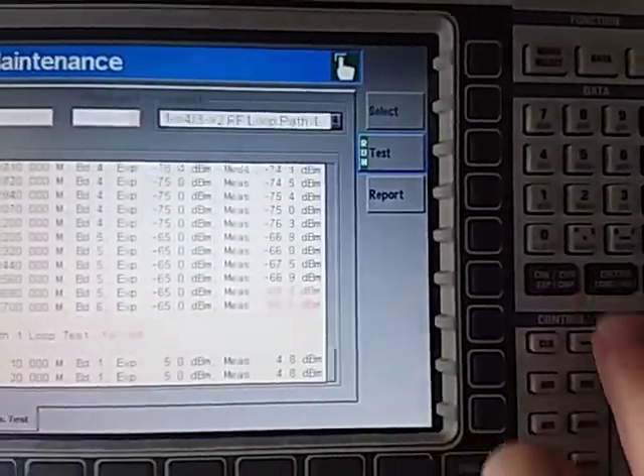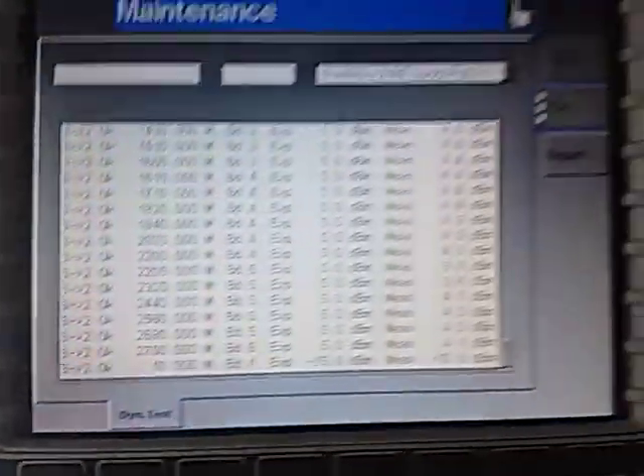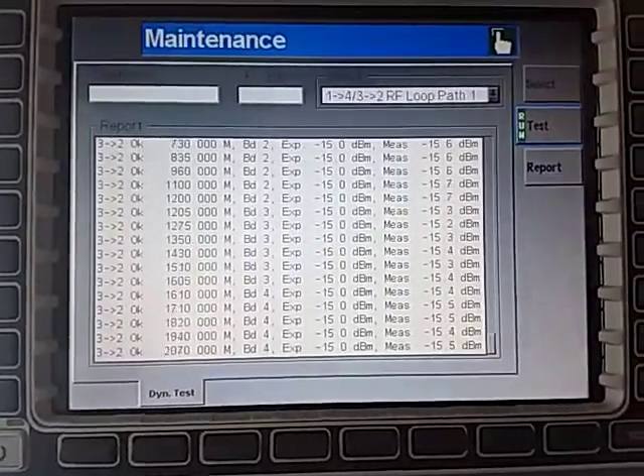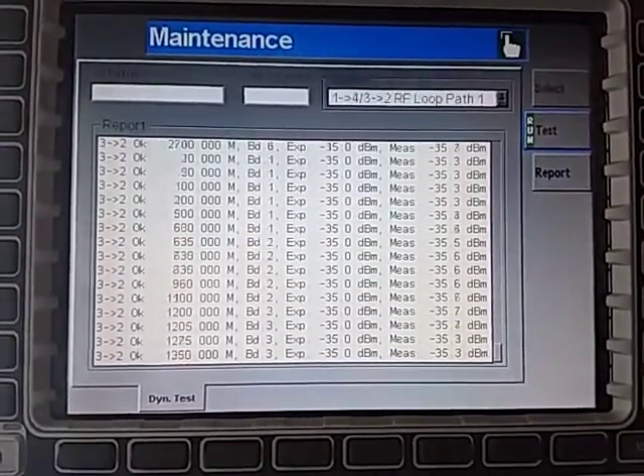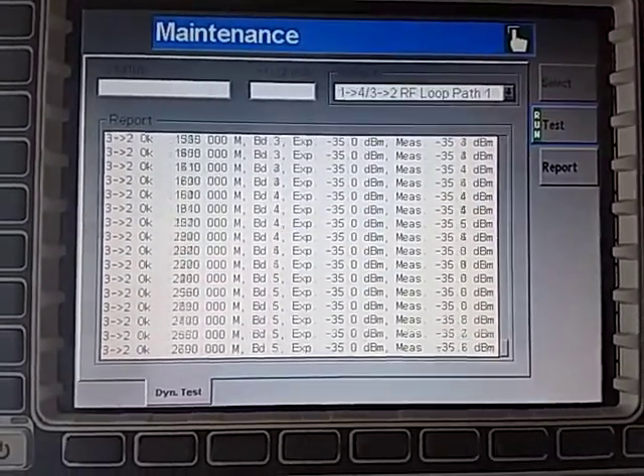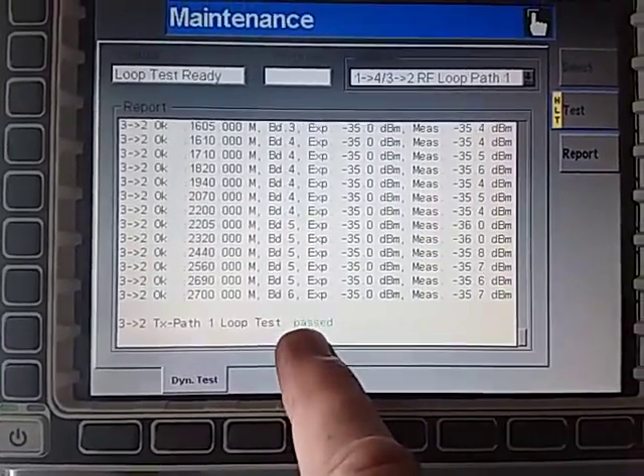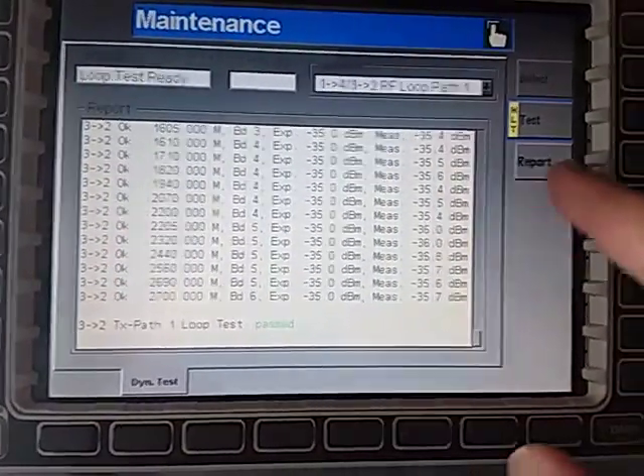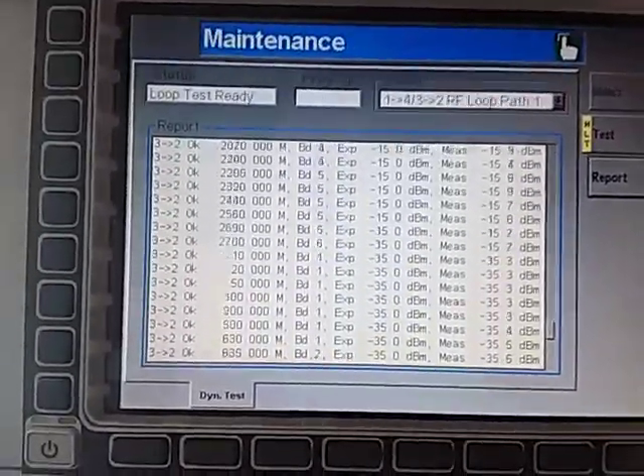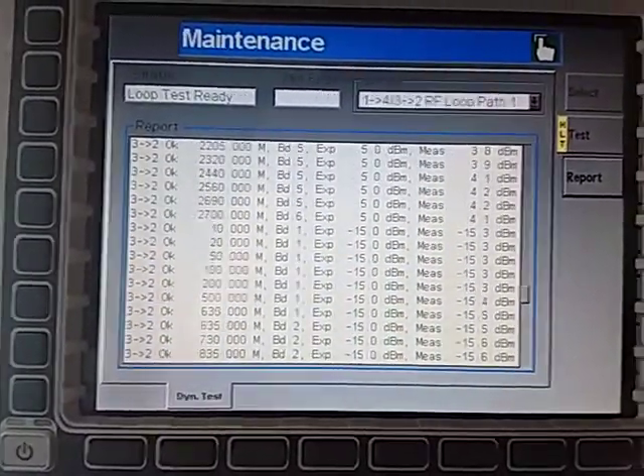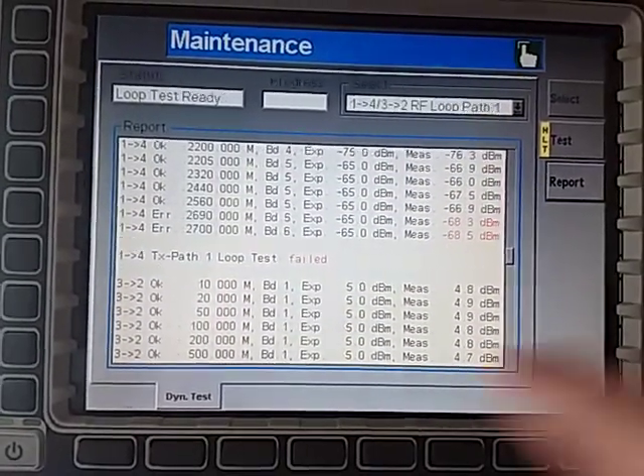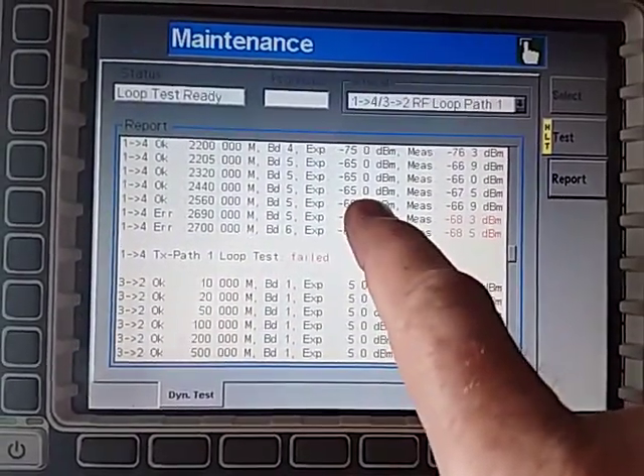We will now note that three to two is being tested and on my analyzer it passes everything on the three to two. We can see that it comes down and it says that it's passed. I can still go into the report screen and I can wind it all the way back and have a look at each one of the tests that we've done on these external loopback tests. You can see the summary for my one to four path has failed.